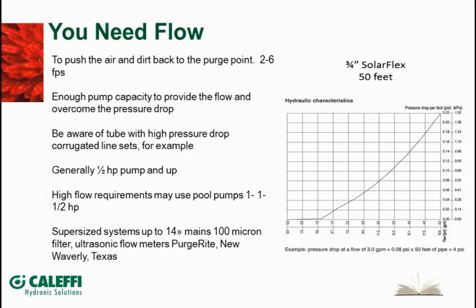Now if you're going to pump the fluid into a system, obviously you're going to need enough pump capacity to give you the flow rate to push the air out of it. In a small residential system, usually the autofill valve, or a small half-horse transfer pump if you're pumping glycol, is going to be sufficient. But if you start doing bigger systems, bigger loop fields on geos or commercial jobs with 2-inch piping, possibly going out to some zone manifolds, you're going to need a little bit more horsepower to give you that kind of flow rate.